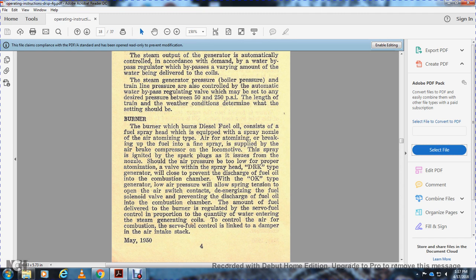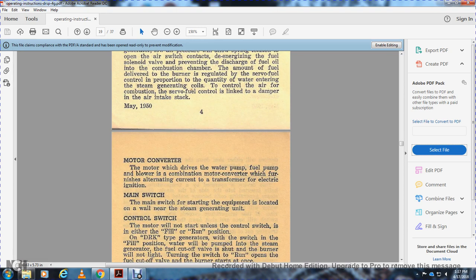On the OK type of generator, low air pressure will allow spring tension to open the air switch contact, de-energizing the fuel solenoid and preventing the discharge of fuel oil into the combustion chamber. The amount of fuel delivered to the burner is regulated by the servo fuel control in proportion with the quantity of water entering the steam generator coil. To control the air for combustion, the servo fuel control is linked to the damper in the air intake stack. Motor converter: the motor drives the water pump and the fuel pump. The combination motor converter furnishes alternating current for the transformer and electrical ignition.